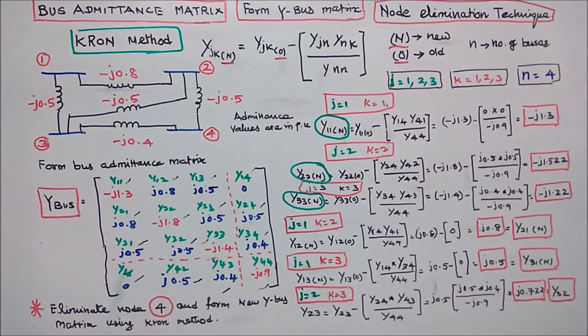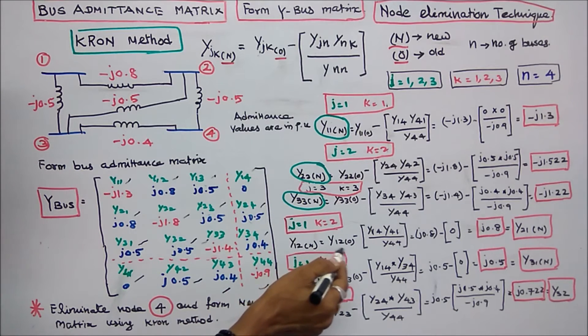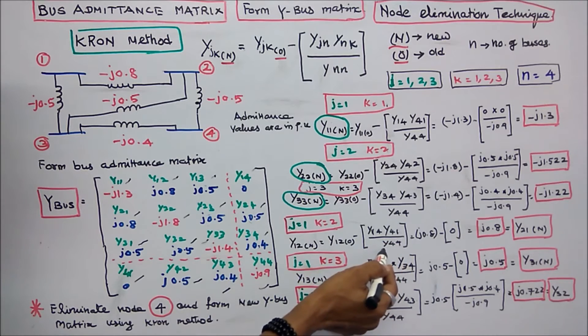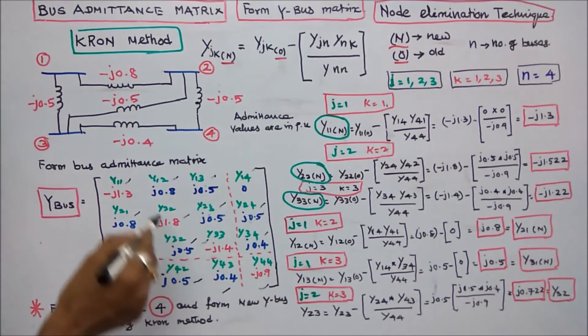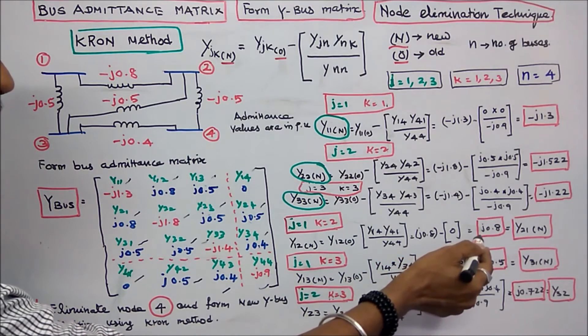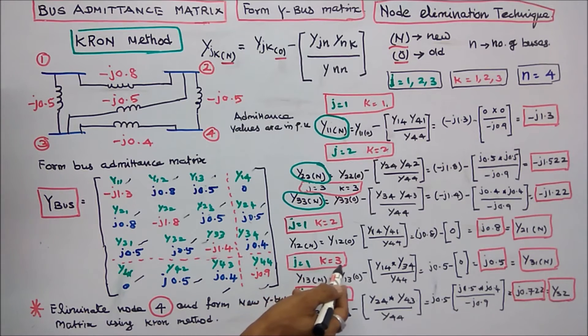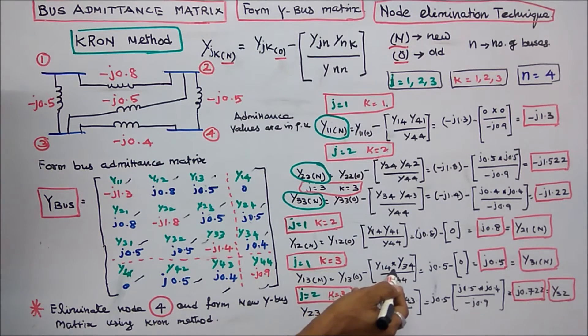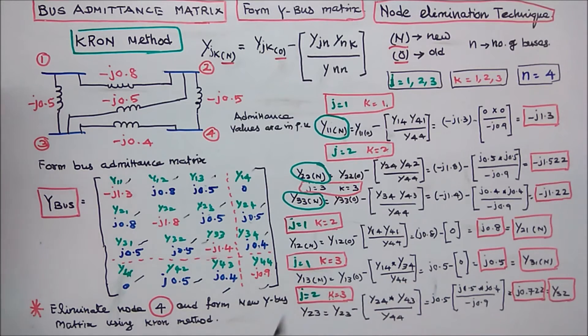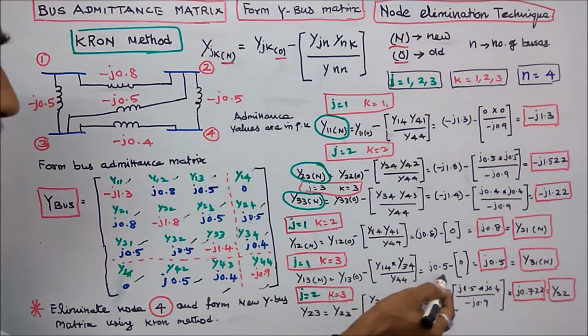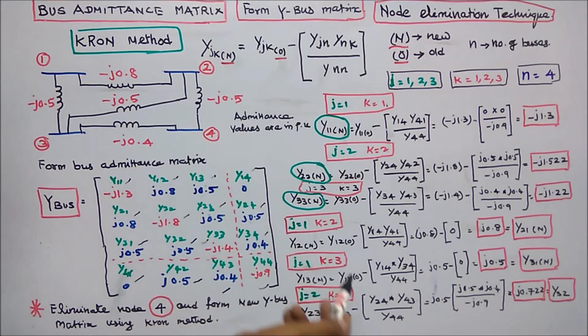The diagonal elements are complete. Now finding the off-diagonal elements. For j=1, k=2: Y12(new) = Y12(old) minus Y14 times Y42 divided by Y44. Since Y14 equals 0, the result is Y12(new) equals plus j0.8. For j=1, k=3: Y13(new) = Y13(old) minus Y14 times Y43 divided by Y44. Since Y14 equals 0, Y13(new) equals plus j0.5, and Y31(new) equals j0.5.